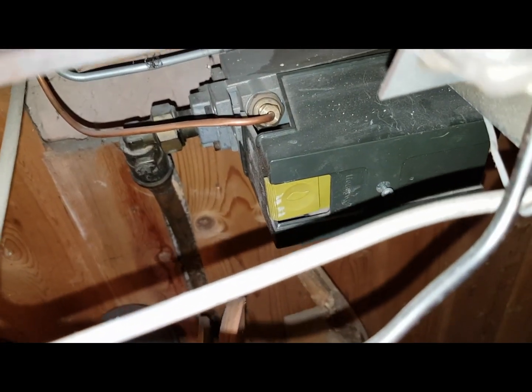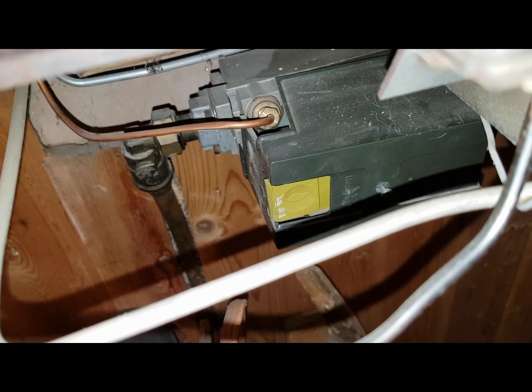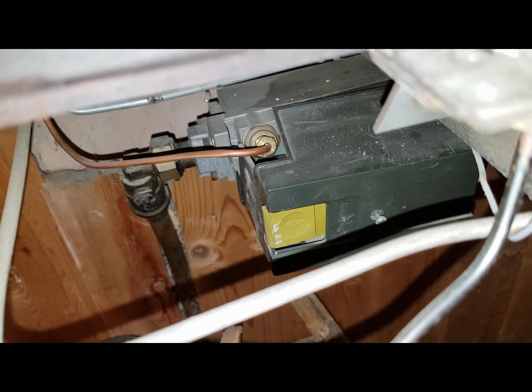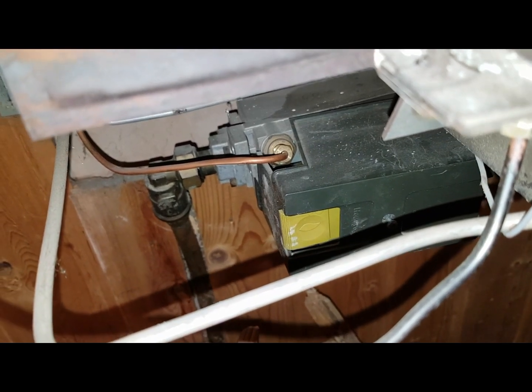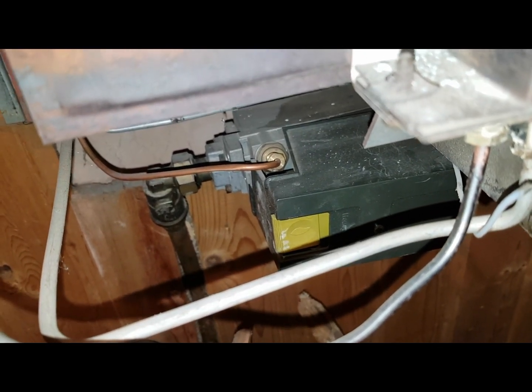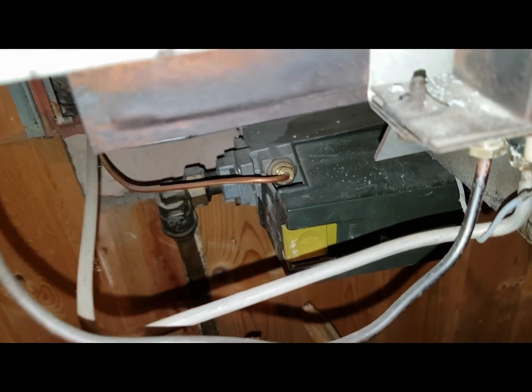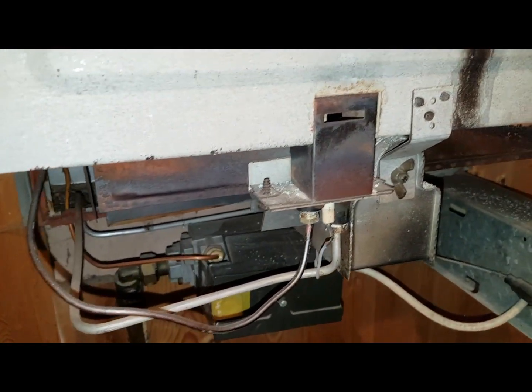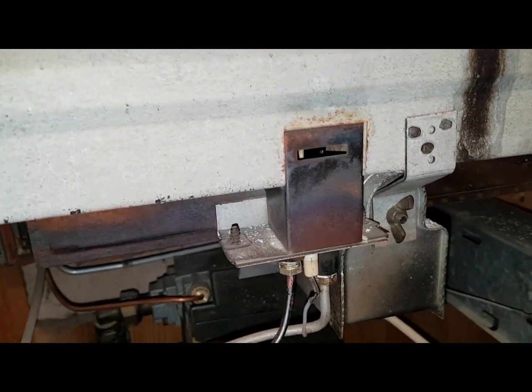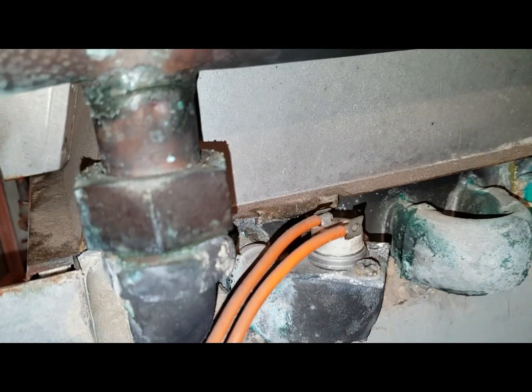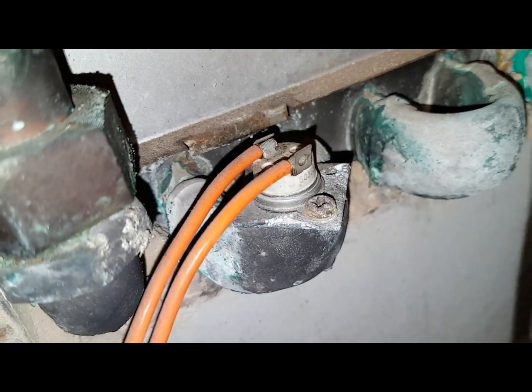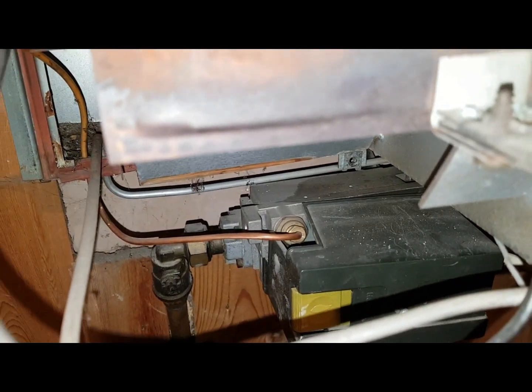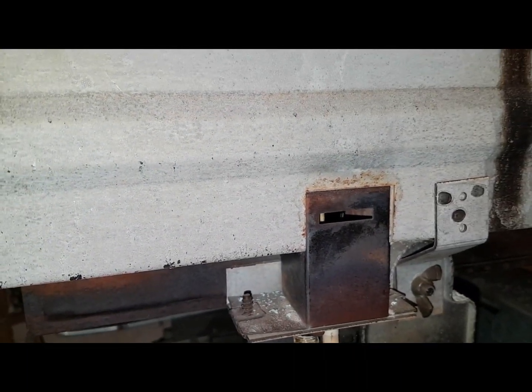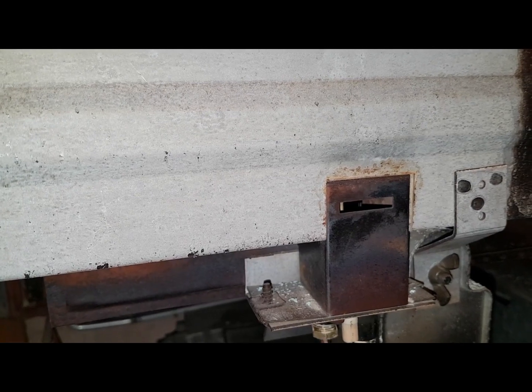When you press that button in, the green button, that pushes on the thermoelectric valve. After 30 seconds it keeps that thermoelectric valve open and allows the gas to light the pilot, and that circuit then keeps the pilot light staying on so that it can light the main burner. Now if that goes open circuit, that will cut the voltage, close the thermoelectric valve, and shut off the gas to the pilot light, and that's what you call the flame failure device.